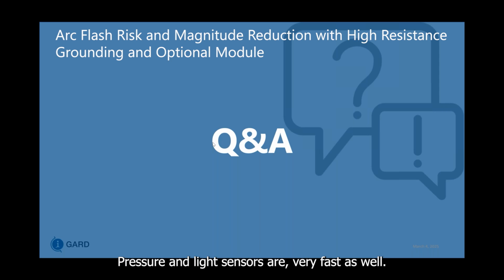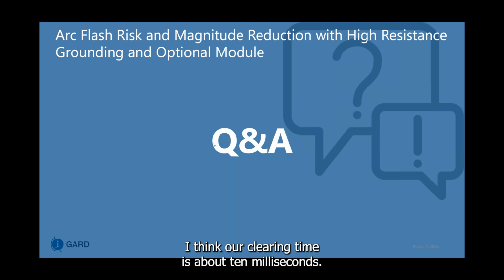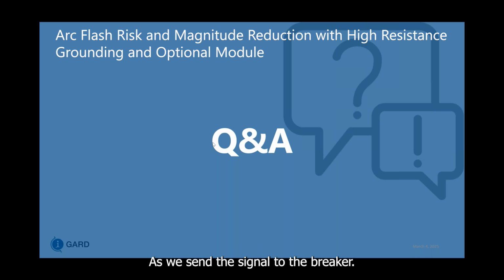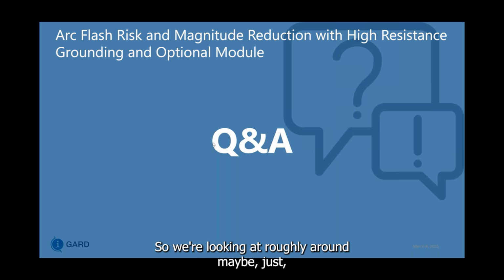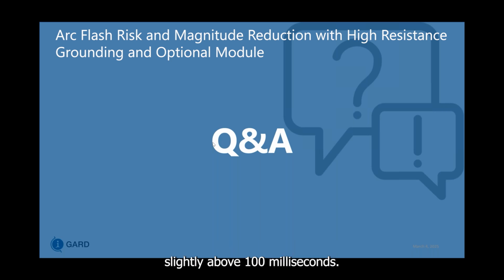Pressure and light sensors are very fast as well. I think our clearing time is about 10 milliseconds as we send the signal to the breaker, and the breaker would typically be 5 cycles. So we're looking at roughly around maybe just slightly above 100 milliseconds here.